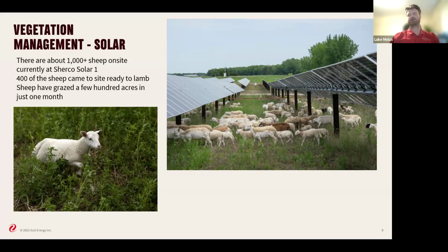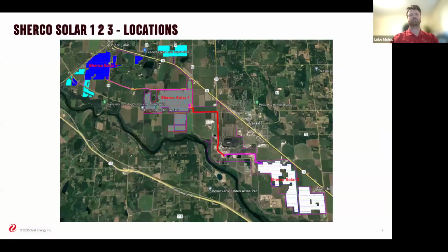In your perfect world, you'd want your array to be completely contained within one section of land, so you don't have to travel across roads or to far areas. It does increase your cost a little bit due to having to run your medium voltage cable, your 34.5 cable, back to wherever you're tying it into. So there is a little bit of increased cost there, but we do try to keep it very tight, to get as many same blocks as you can.